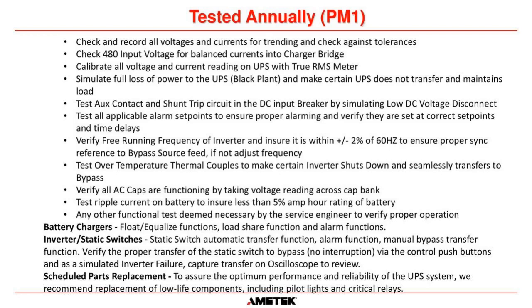Now, at most plants, you'll have the operators go around on a daily or a weekly basis, checking all of the meters on your critical equipment. We've all seen it. You've got the pencil or Sharpie mark on the meters to tell you what they should be. Well, those readings are useless, absolutely useless, if they're not reflecting what is actually being seen by the UPS. So you have to make sure that when you're checking all the voltages and currents within the system, that you are comparing them with what the digital or analog meters are saying on the UPS, so you know what's going on.